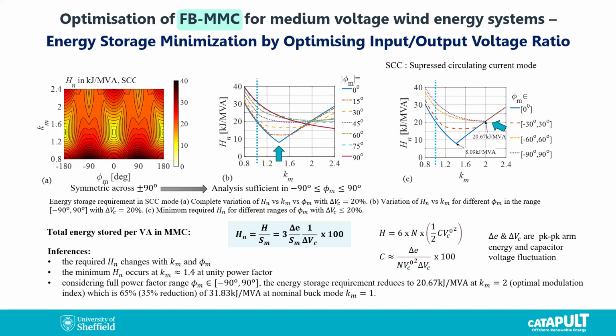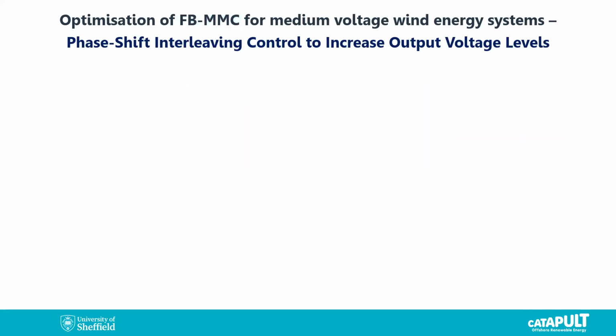Okay, so next slide. Here is the second step in our optimization approach. First was how we can reduce the capacitance, and now it is how we can increase output voltage levels. For the minimum number of cells, or submodules, that we use, we would like to get as many output levels as possible, as that increases power quality, so we can get rid of the filter. The approach that we take is phase shift interleaving. So we talk about an interleaving angle between the upper arm and lower arm voltages. If you can click 2 times.